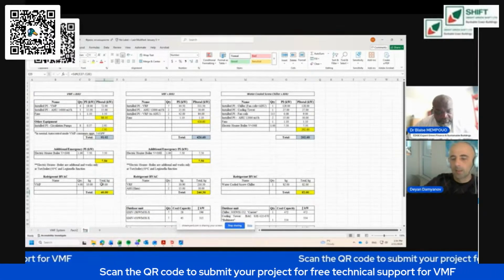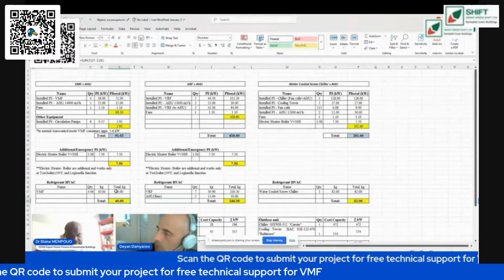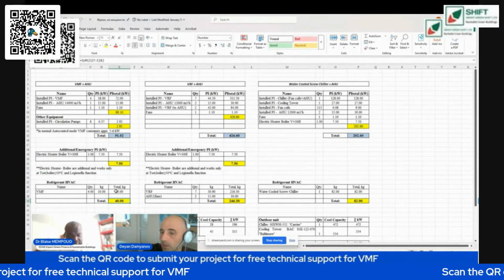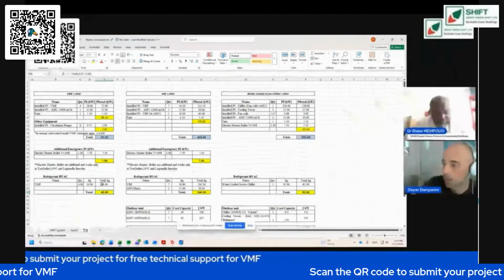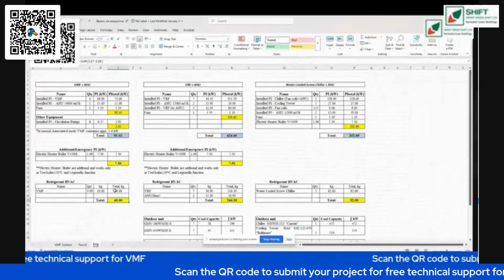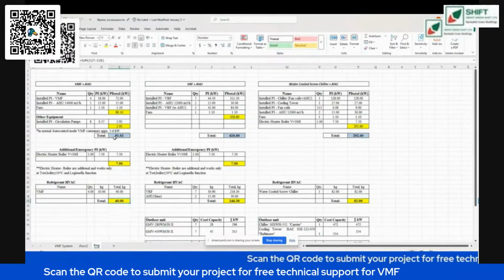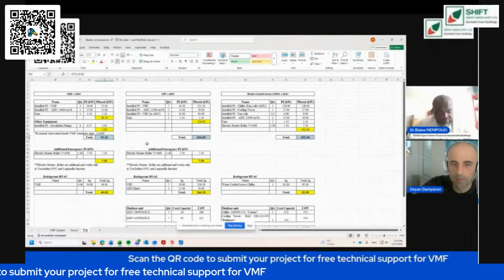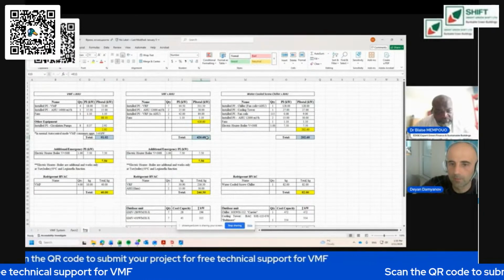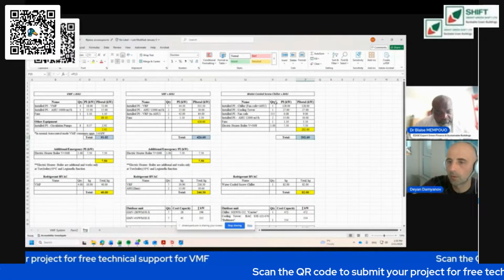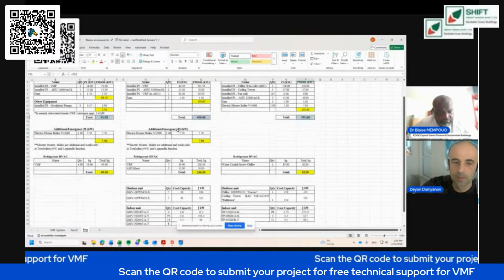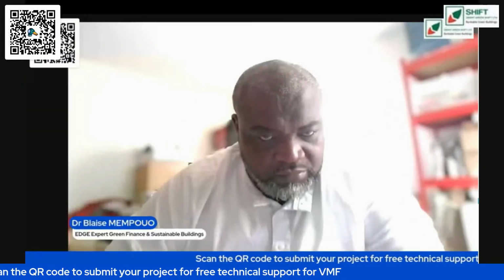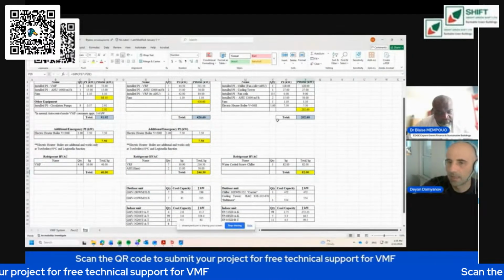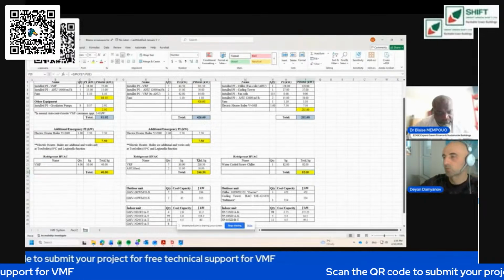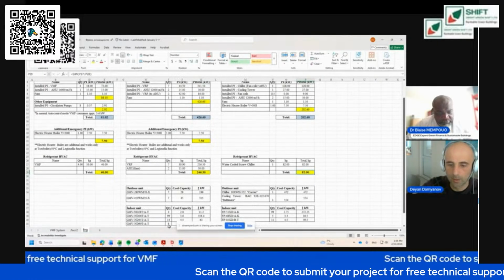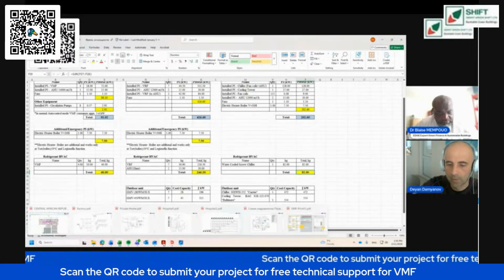Normally we produce this kind of comparison sheet for every project we work on, and you can see the differences are significant. I repeat: 91 kilowatts for the VMF concept, 426 for VRF plus air handling unit, and 202 kilowatts for water-cooled screw chiller plus air handling units. 40 kilograms versus 246 versus 82 — massive, massive differences. This is the structure for every project we do as a pre-design.